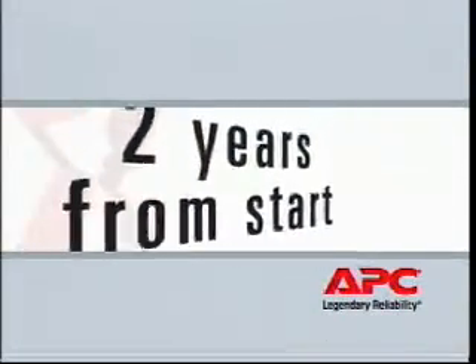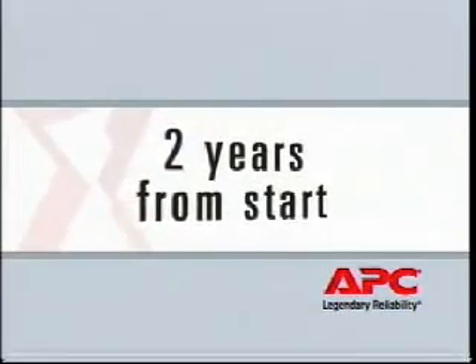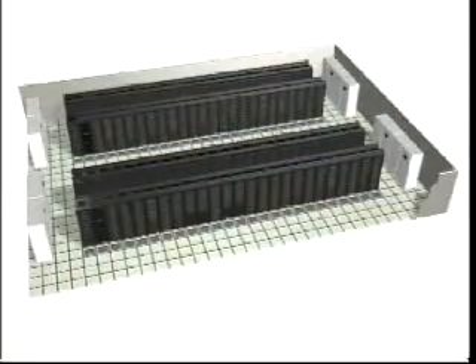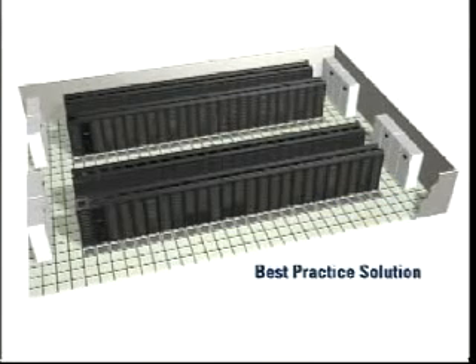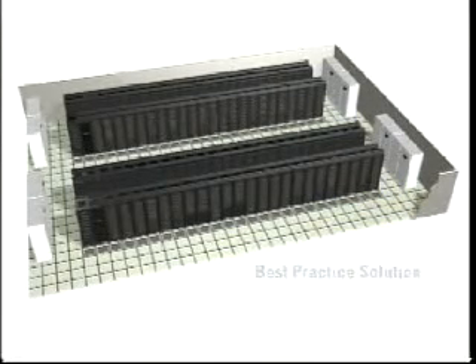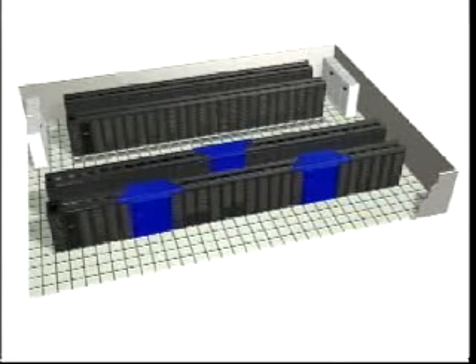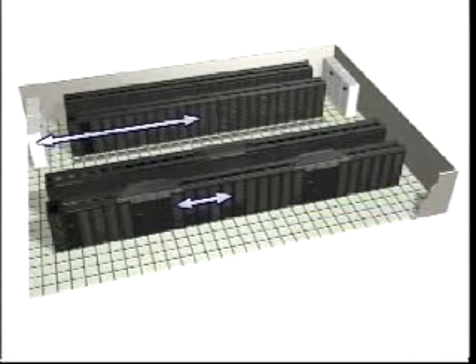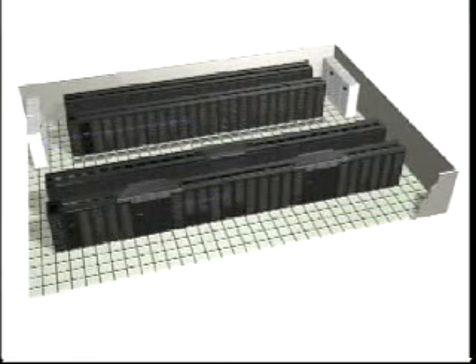It is now 2 years after the initial data center installation. The data center manager begins to implement, in stages, a best practice solution. He reconfigures two of the four rows in the data center for in-row cooling. Four legacy CRAC units are removed and three network air IR units are installed. In-row cooling not only shortens the path between the hot air and the heat removal device, it also removes from the cooling equation the unpredictable nature of cold air delivery.